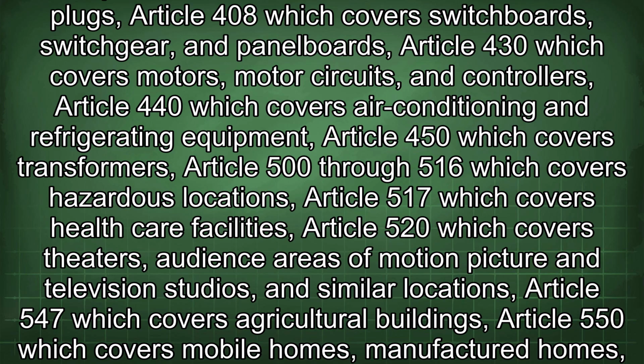Article 310 which covers conductors for general wiring, Article 400 which covers flexible cords and cables, Article 404 which covers switches, Article 406 which covers receptacles, cord connectors, and attachment plugs, Article 408 which covers switchboards, switchgear, and panelboards, Article 430 which covers motors, motor circuits, and controllers, Article 440 which covers air conditioning and refrigerating equipment.